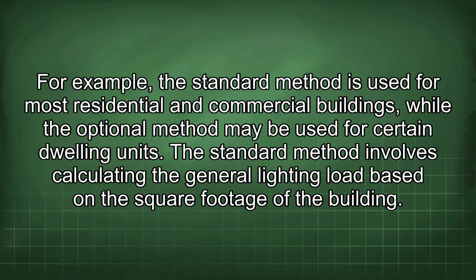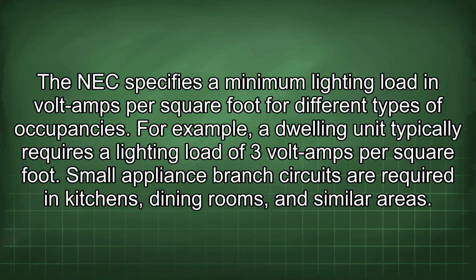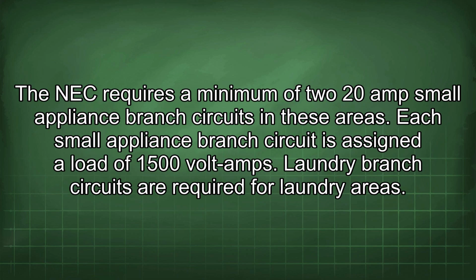The standard method involves calculating the general lighting load based on the square footage of the building. The NEC specifies a minimum lighting load in volt amps per square foot for different types of occupancies. For example, a dwelling unit typically requires a lighting load of 3 volt amps per square foot. Small appliance branch circuits are required in kitchens, dining rooms, and similar areas. The NEC requires a minimum of 2 20 amp small appliance branch circuits in these areas. Each small appliance branch circuit is assigned a load of 1500 volt amps.